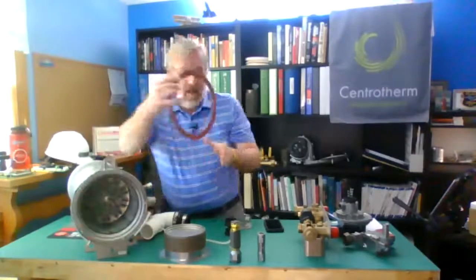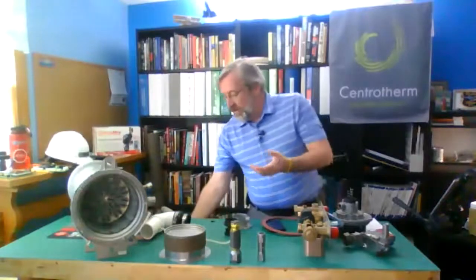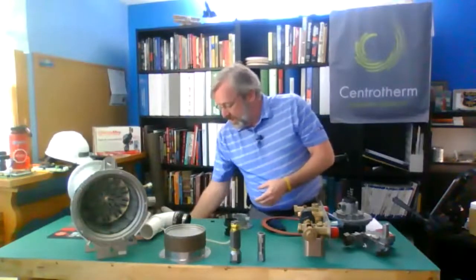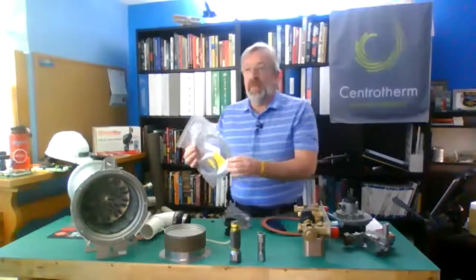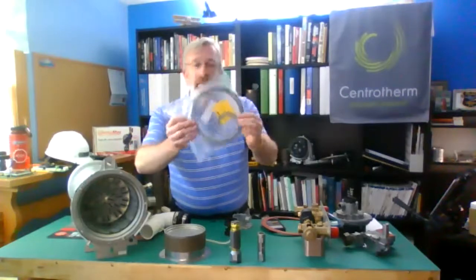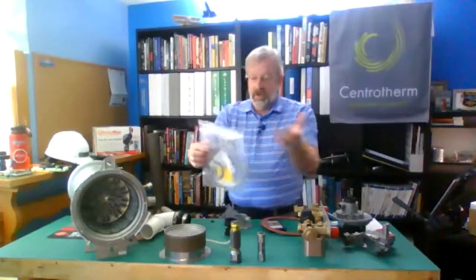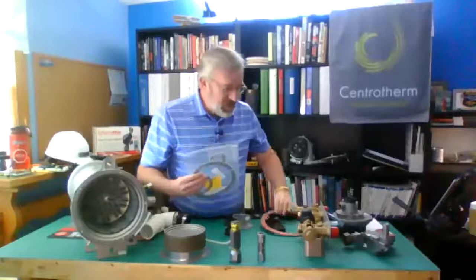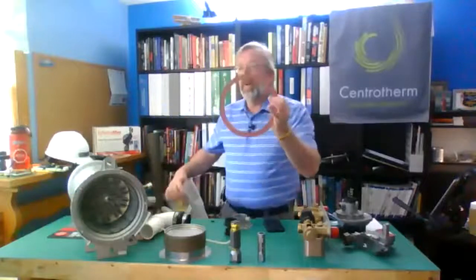That's okay. If you're working with some of the other wall-hung Lochinvar boilers, some of the older 5-to-1 style, you're going to have this fiber gasket. This is actually the gasket for my boiler, which we're going to be servicing on Friday. It has a felt gasket. The newer 10-to-1 models, you're going to get that rubber gasket, okay?